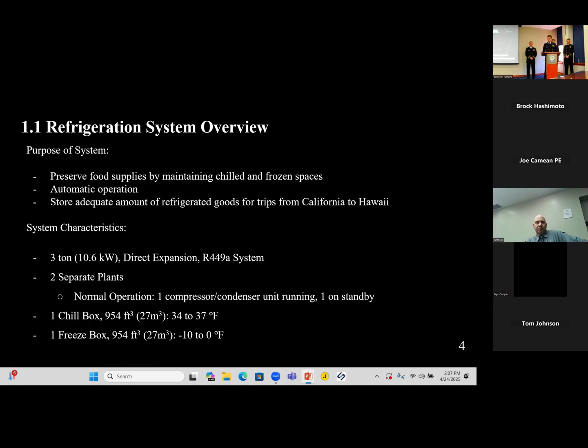The system is comprised of a 3-ton direct expansion R449A refrigerant system. There are 2 separate plants, with 1 compressor and condenser unit in each plant. One is always in operation with the other on standby for redundancy purposes. Lastly, there are 2 chilled and refrigerated spaces. There's 1 chill box with a volume of 954 cubic feet, maintained from 34 to 37 degrees Fahrenheit, and a freeze box with the same volume of 954 cubic feet, maintained from -10 to 0 degrees Fahrenheit.